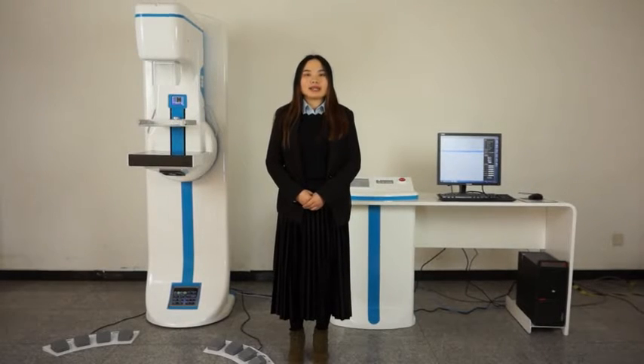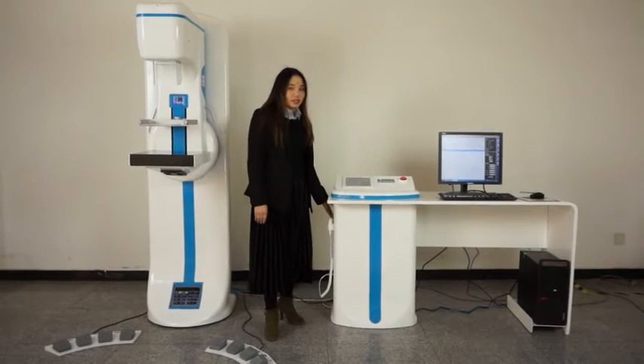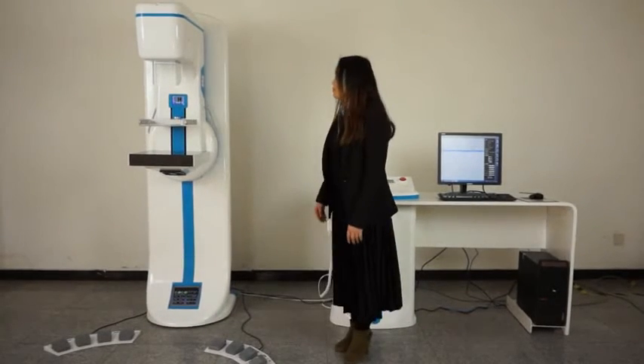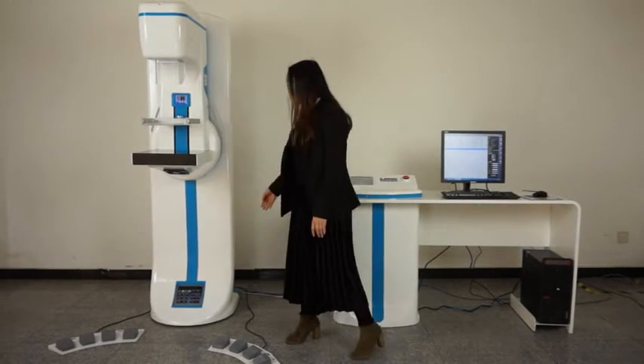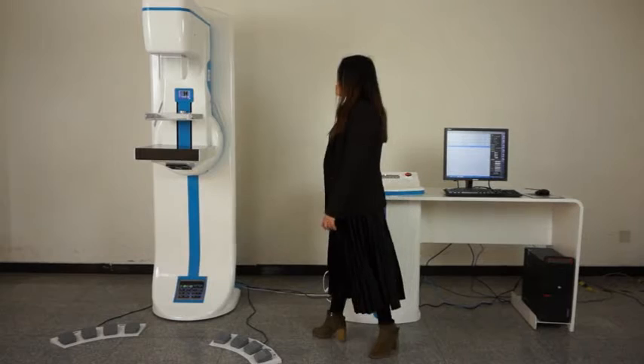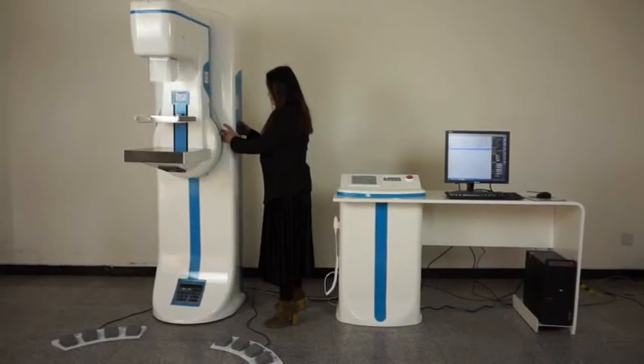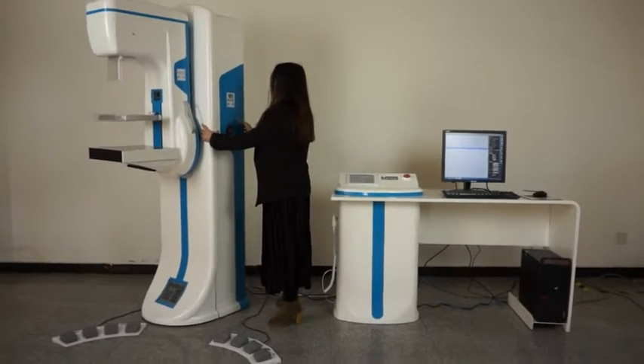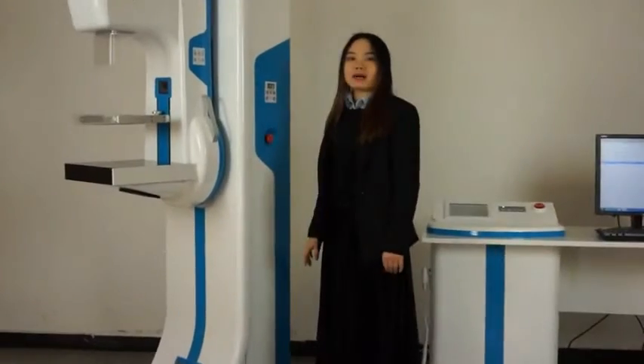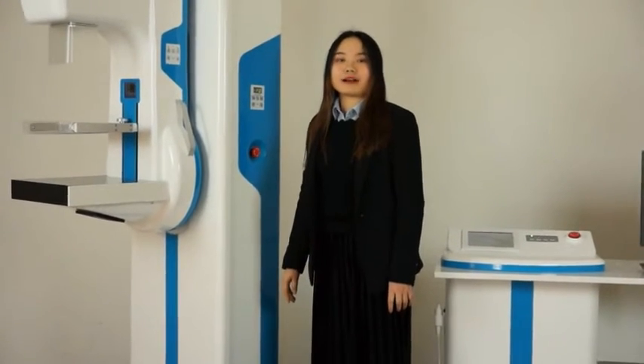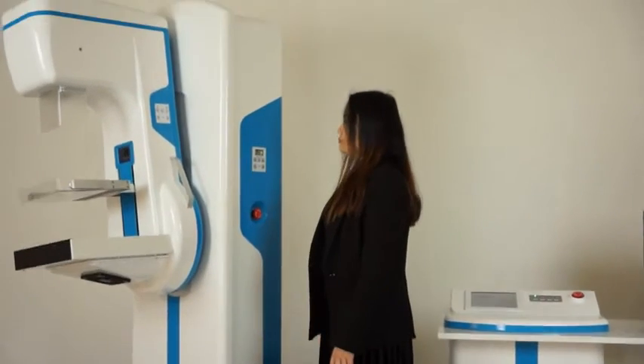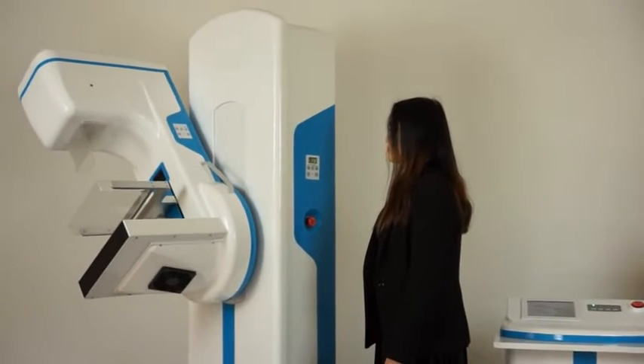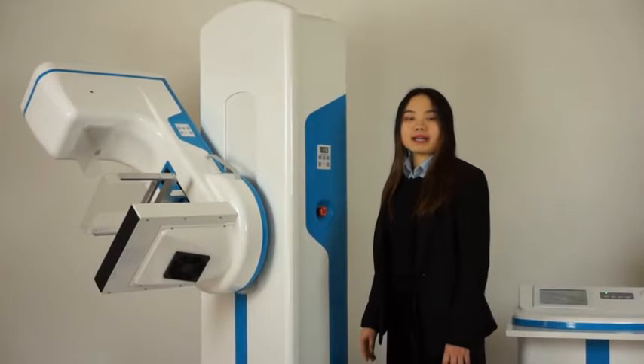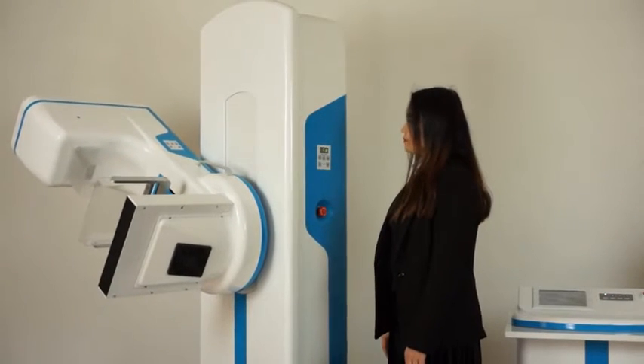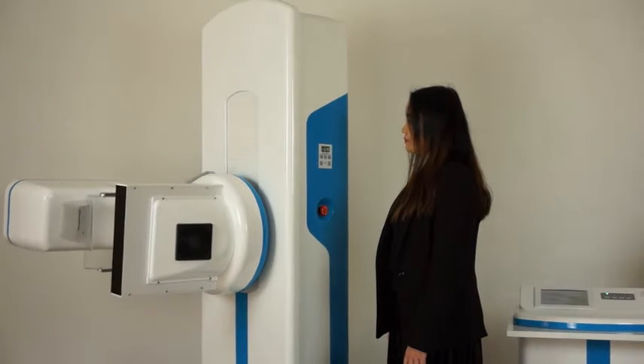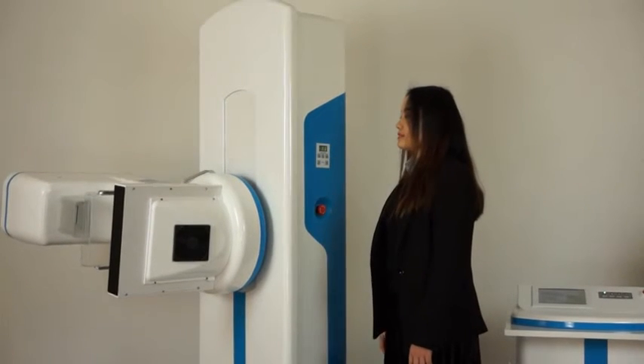Next, I will show you the operation and movement of the machine. First, plug in the machine here, power on here, and when you hear the beeping sound on power up and the LCD screens come on, that means the machine is ready to work. There are two panels on both sides of the frame. It shows the angles of rotation, including one button for lateral position by minus and plus 45 degrees, like this. And isocentric rotation minus and plus 90 degrees. And also one reset button.